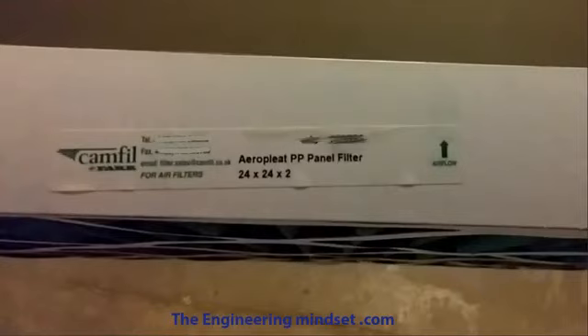Now on the side of the primary filters, you should have some details on there about who the manufacturer is. You'll have an order number there so you can track it and reorder it. You should also, if it's a good manufacturer, have an arrow indicating the direction of the airflow, and you've also got some dimensions there for the size of the filter.